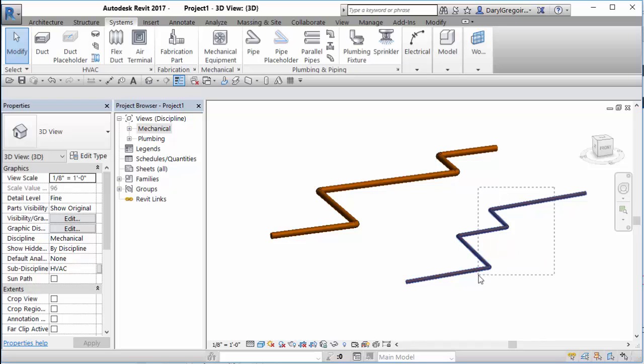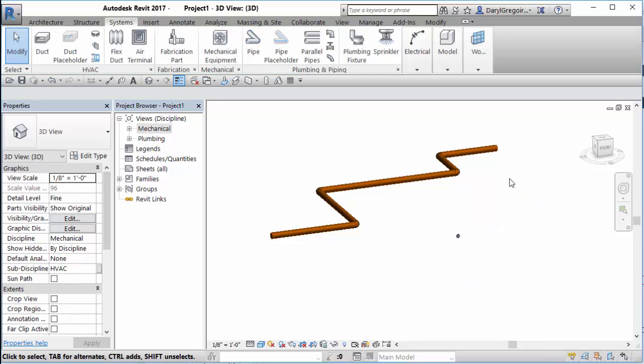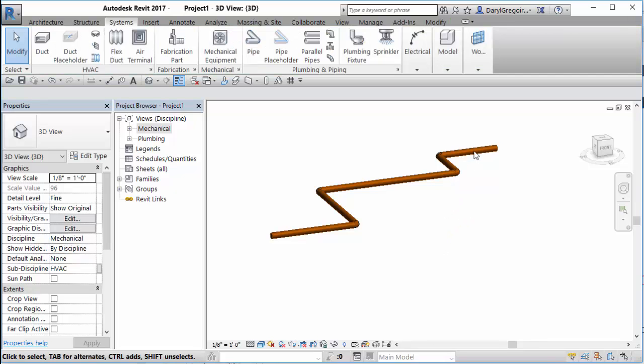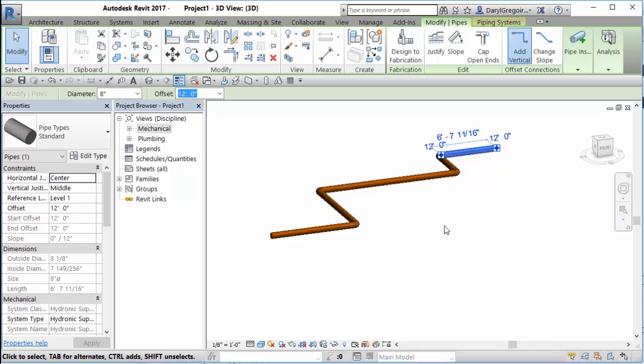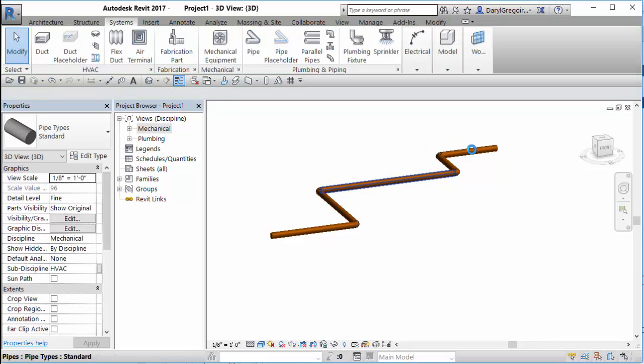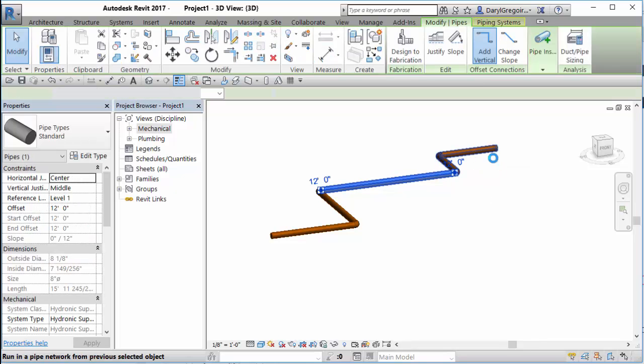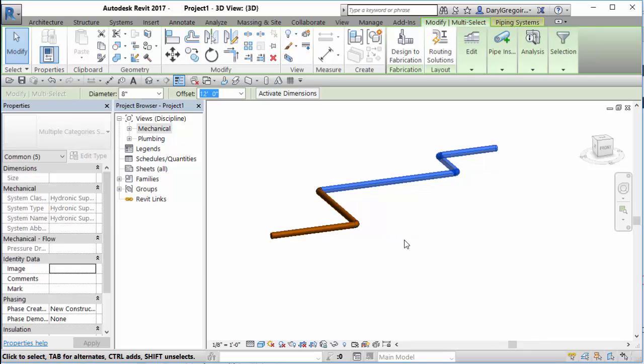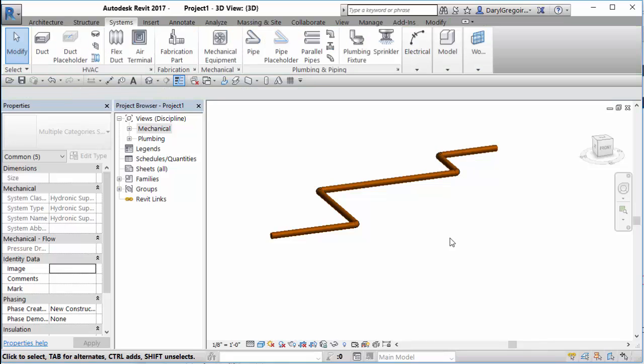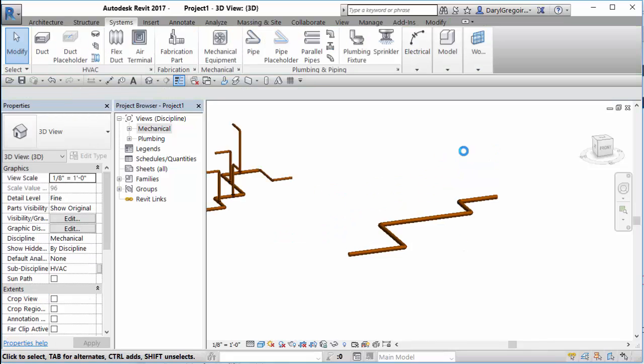Now if you've got piping that's already in there and you need to change the slope after the fact, you have to select the group of pipes. Using our tab key, you can hover and hit tab — it'll basically find that string. If you try to slope only one segment of a connected line, Revit doesn't like it because it prefers to have the whole run sloped, not just one part.